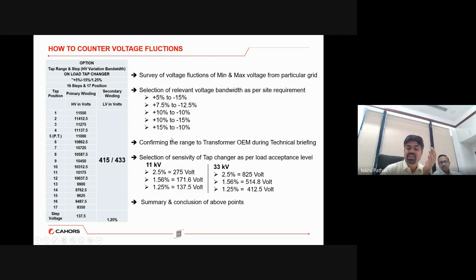So these tap ranges can be kept in steps of 2.5%, 1.56%, or 1.25%, which means the tap will change every 275 volts, or every 171 volts, or every 137 volts. Same for 33 kV, which is the higher side, because the 11 to 33 changes happen. So whether 412 volts is sufficient for changing, or it is too much, because the fluctuation will also increase the number of tap operations.